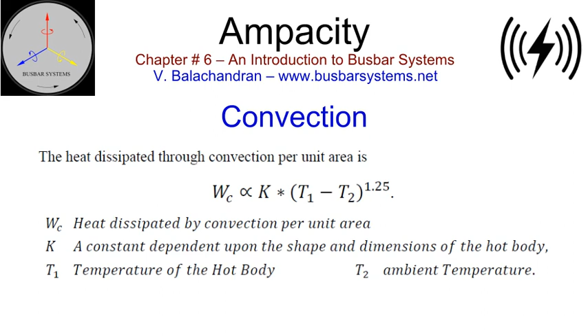A conductor, when installed outdoors, will be subjected to wind in the horizontal plane. The efficiency of heat evacuation will depend upon the wind speed. For some busbar systems, such as an isolated phase bus, heat from the conductor may also be evacuated by forced convection or forced cooling. The heat dissipated through natural convection per unit area is proportional to the difference in temperature between the hot body and the ambient to the power 1.25.